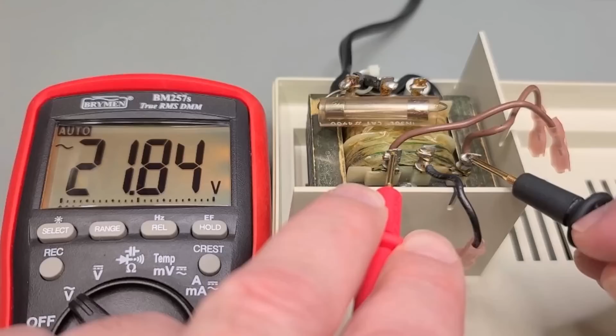I have already tested the fuse with the power unplugged and the fuse is intact. According to the service manual, the secondary of the power transformer should be providing 17.2 volts AC, center tapped. We are seeing a higher voltage here at 21.8 volts, but we have to keep in mind this is with no load, so not of great concern at the moment.